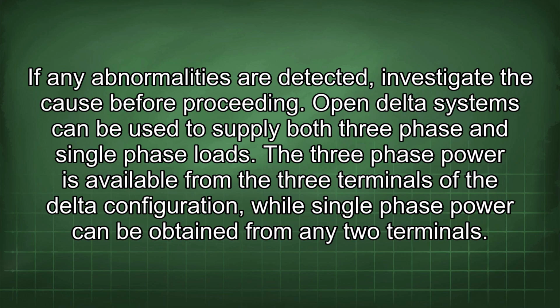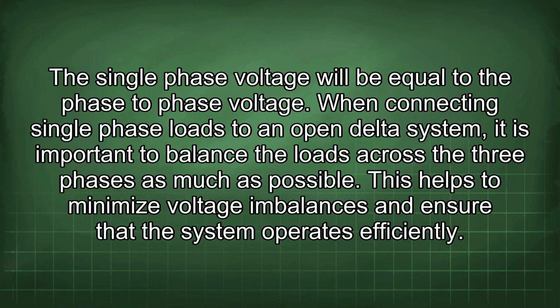Open delta systems can be used to supply both three-phase and single-phase loads. The three-phase power is available from the three terminals of the delta configuration, while single-phase power can be obtained from any two terminals. The single-phase voltage will be equal to the phase-to-phase voltage. When connecting single-phase loads to an open delta system, it is important to balance the loads across the three phases as much as possible. This helps to minimize voltage imbalances and ensure that the system operates efficiently.